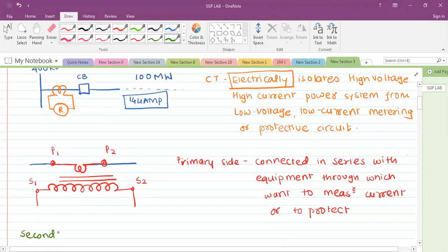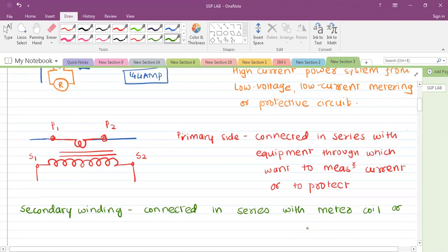and the secondary winding is connected in series with the meter or relay coil. For metering purpose, it is connected with the meter. For protection purpose, it is connected with the relay coil. So here, on the secondary side of the CT, we connect either a meter coil or a relay coil. I am indicating a relay right now because we want to discuss it for the protection purpose. Fine.